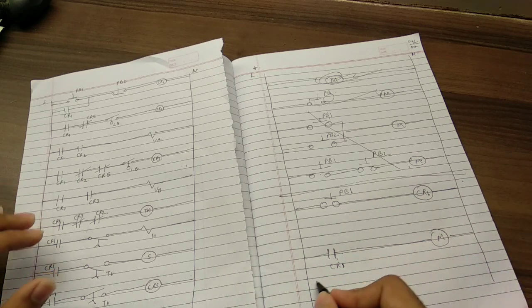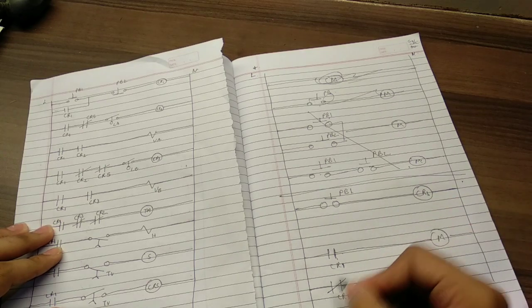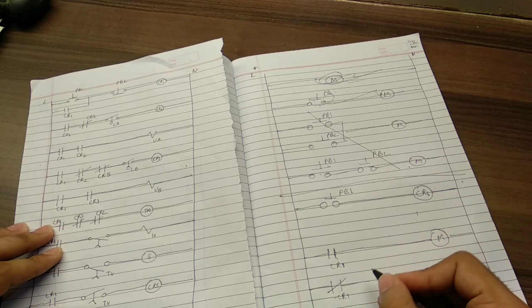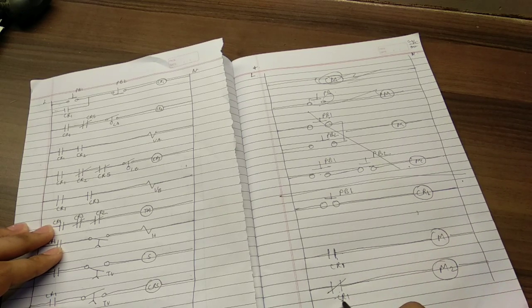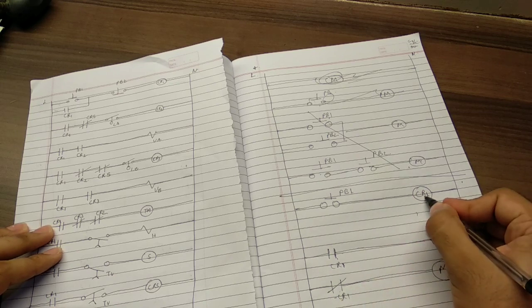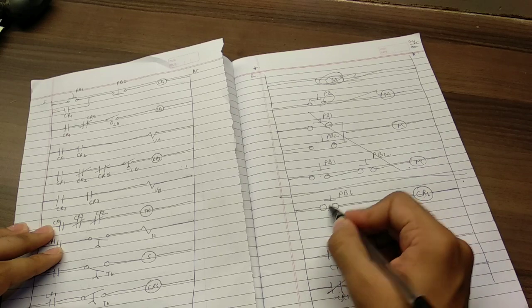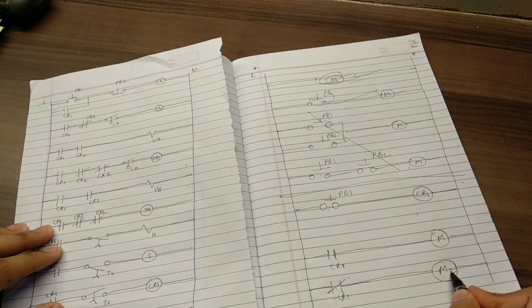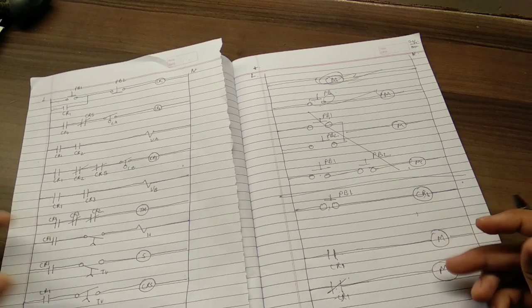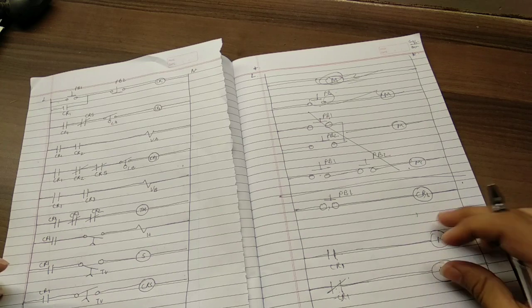Simple as that. Now there is another terminology in control relay, that is this CR1 again. So if I'm using the same name, that means I'm referring to that coil. So if I have this M2, this means that when CR1 is de-energized, this would be on. So that means that if I press the push button, this switch will open up and motor 2 would be off. So effectively I've made a logic wherein motor 1 and motor 2 would be alternatively on.